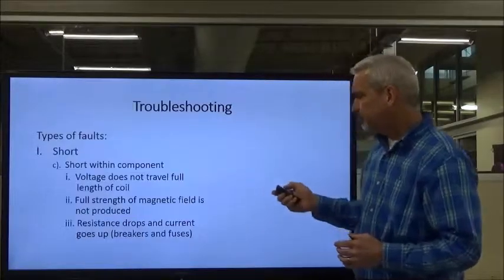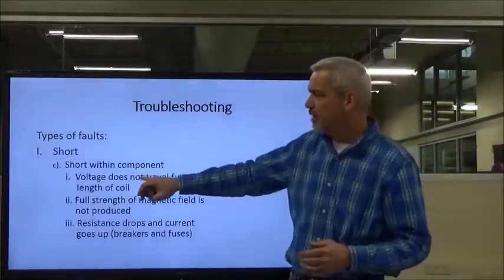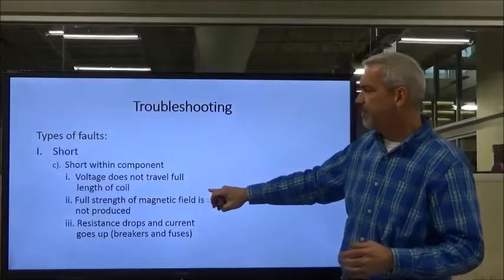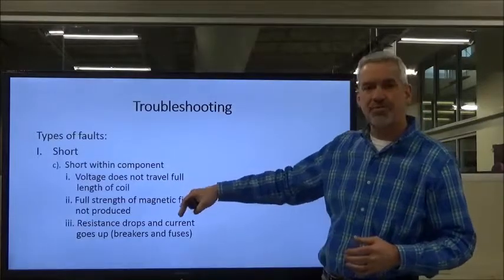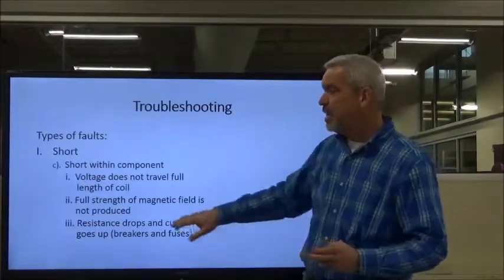Going back — when the resistance drops, the current goes up, and we start popping breakers and fuses. If you've got a breaker or fuse you're having to replace or reset, it's telling you something. If it does it once, you can probably get away with it. If it comes back again, even three, four, five hours later, you're starting to see problems — degradation. Something's going on. Don't ignore it, don't reset it, and please don't put bigger fuses in it.